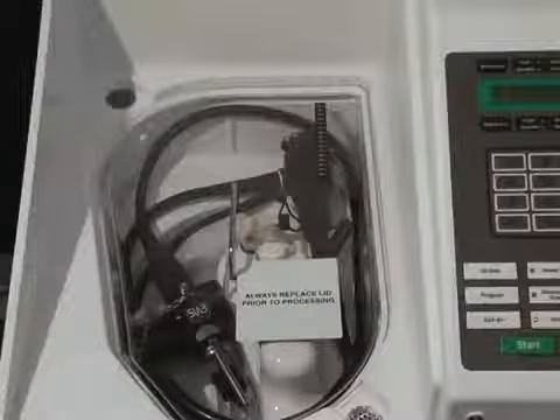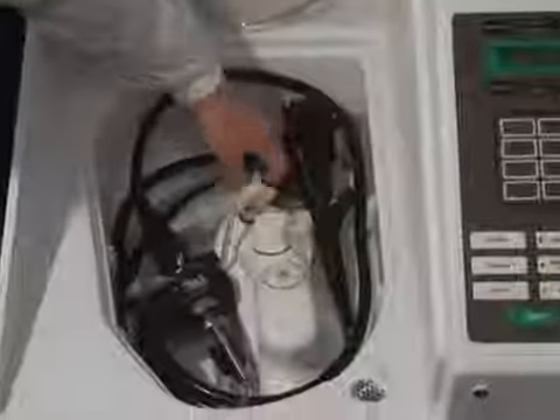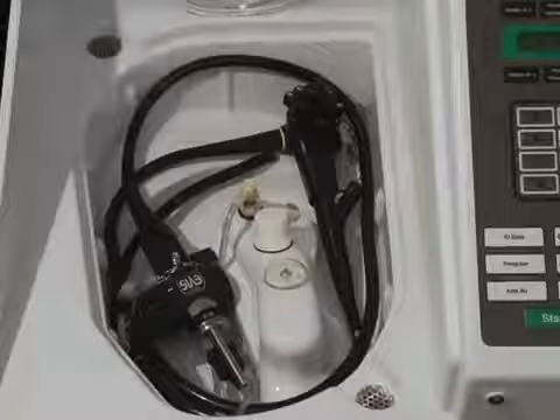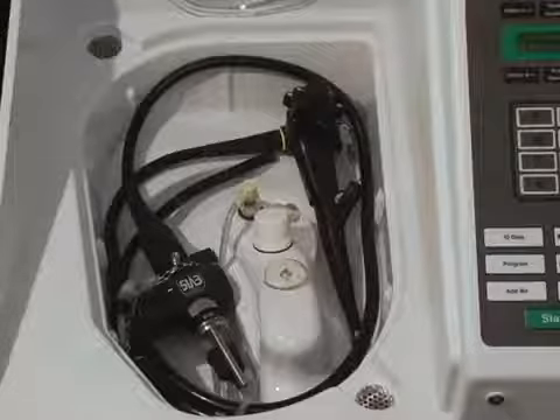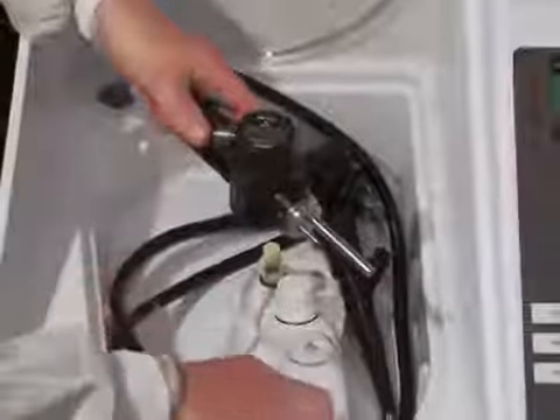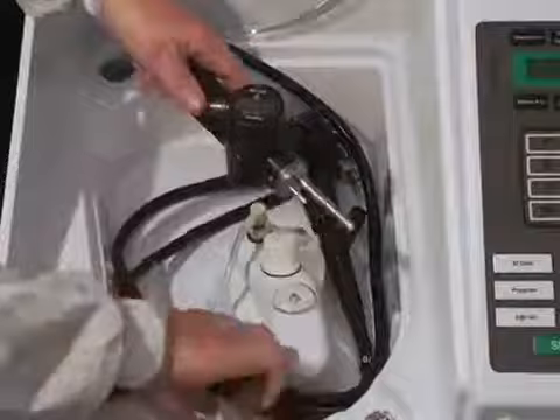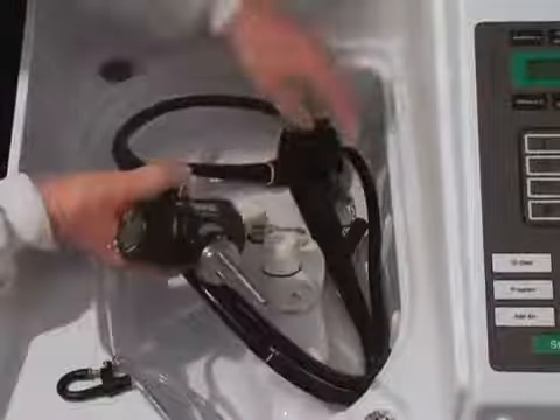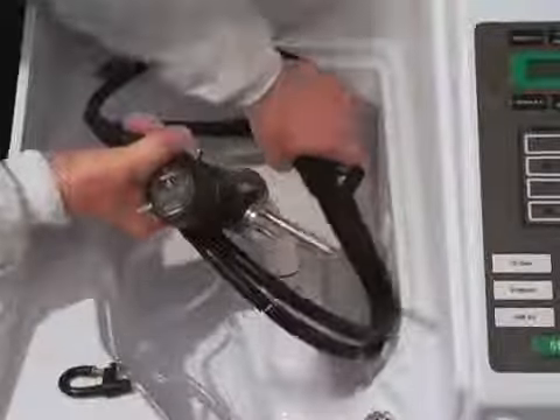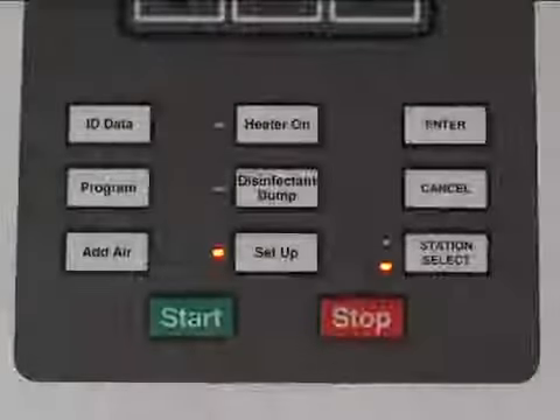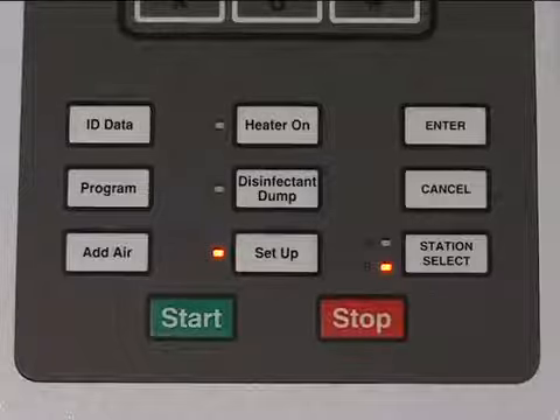Open the basin lid. Remove the floating lid and store it behind the lid supports. Remove the accessory bag. Dry and store the parts. Remove all connectors from the endoscope. Remove the endoscope from the basin. If the endoscope is being stored, thoroughly dry all surfaces with a clean, lint-free cloth. We'll review additional keys on the control panel.